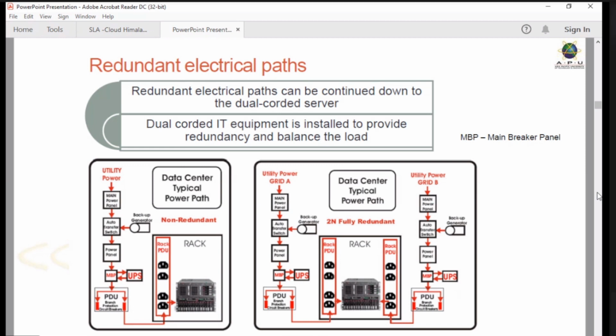If power doesn't come from the utility, then it switches to the backup generator. Then there is a power panel, and then MBP, the main breaker panel. If any issue comes up, it totally disconnects for safety, and this main breaker panel is connected to the UPS, which provides a different source. Finally the connection goes to the PDU, where your servers are connected, along with rack PDUs where your servers and devices are connected.